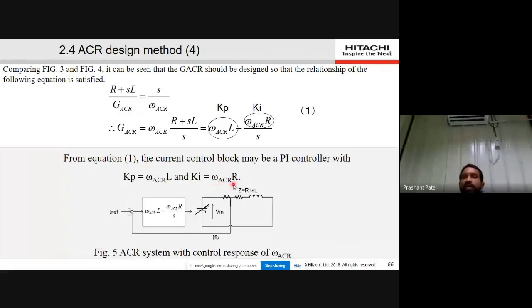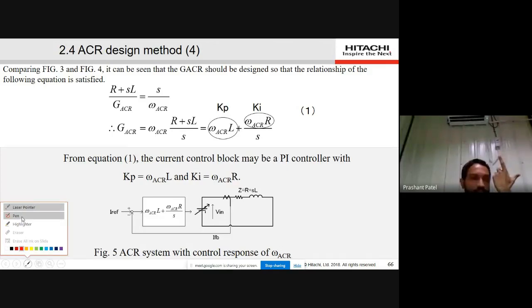Normally for the inner current loop, we know it should be faster than the voltage control loop. Sometimes we take the inner current loop 10 times faster than the voltage control loop, or between 5 to 10 times faster than the AVR loop. So suppose your AVR loop is 100 radian per second, you can select your ACR between 500 to 1000 radian per second.